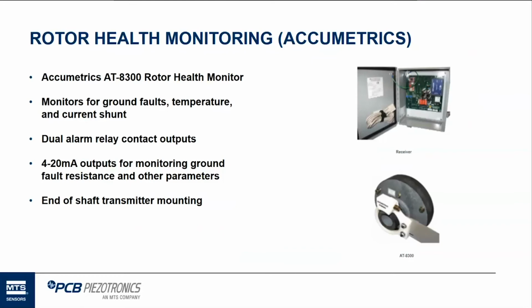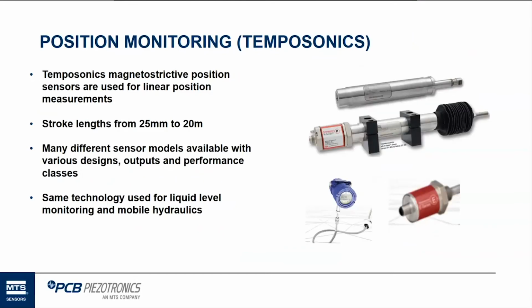Going over to TEMPOSONICS for position monitoring. TEMPOSONICS provides position and also liquid level sensors. They're really big in mobile hydraulics. If you need sensors for mobile hydraulics, mobile equipment relies on that. There are a lot of different stroke lengths. So if you're monitoring a WICKET gate, they can go from 25 millimeters to 20 meters. Not that you would ever need to go that far on a WICKET gate, but that's their capability within TEMPOSONICS.